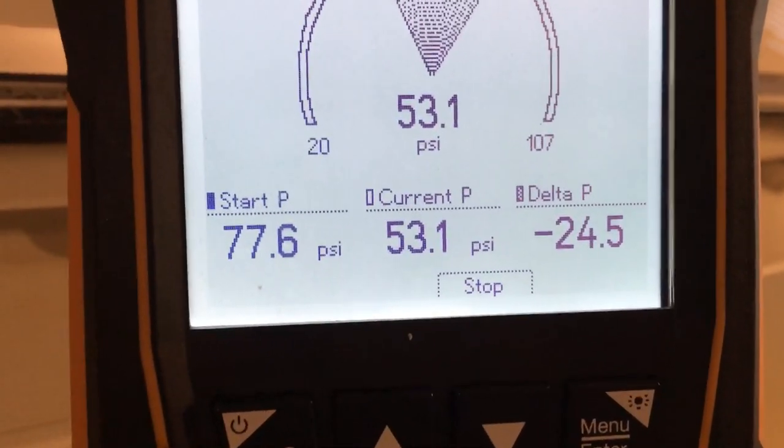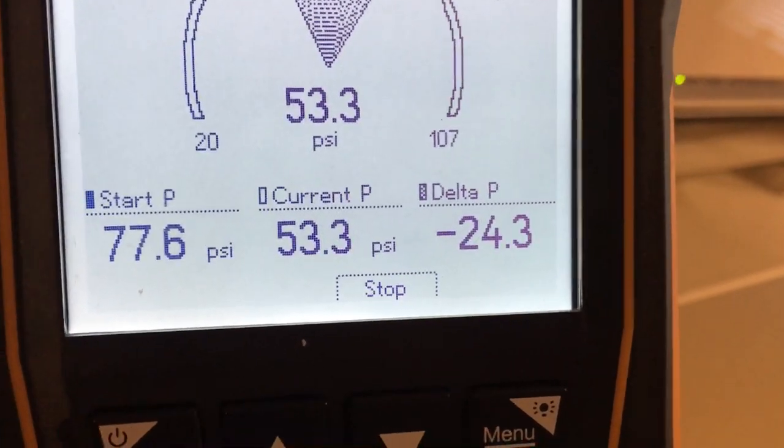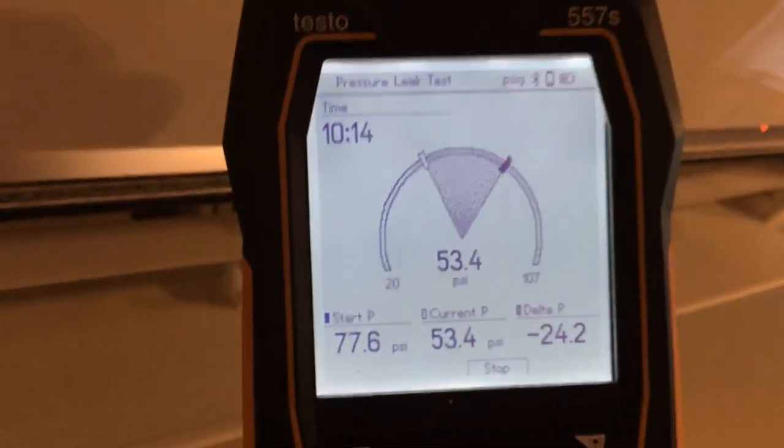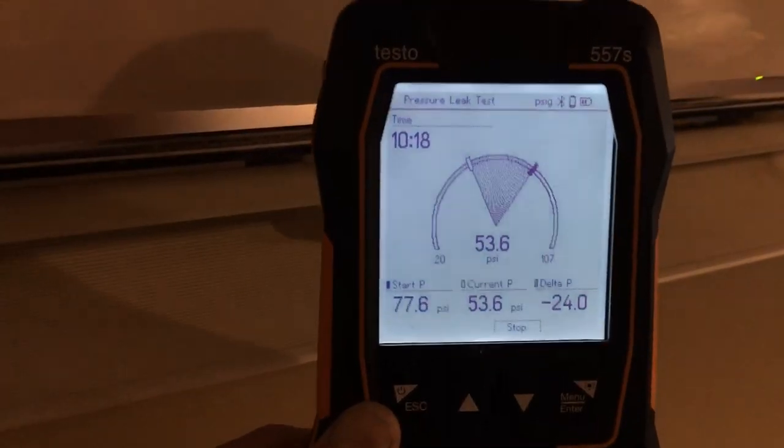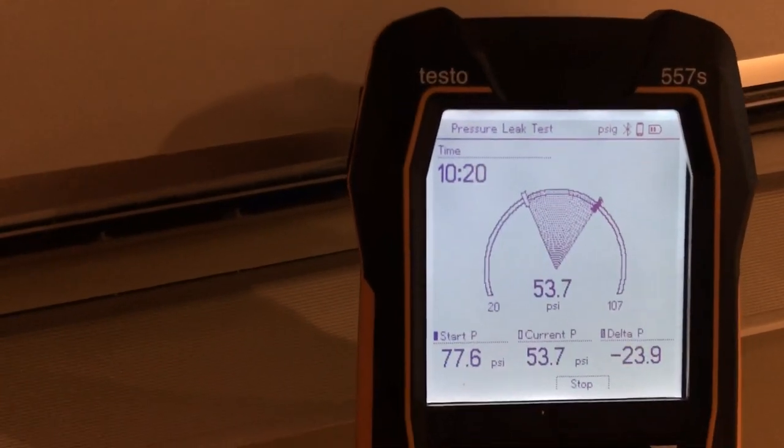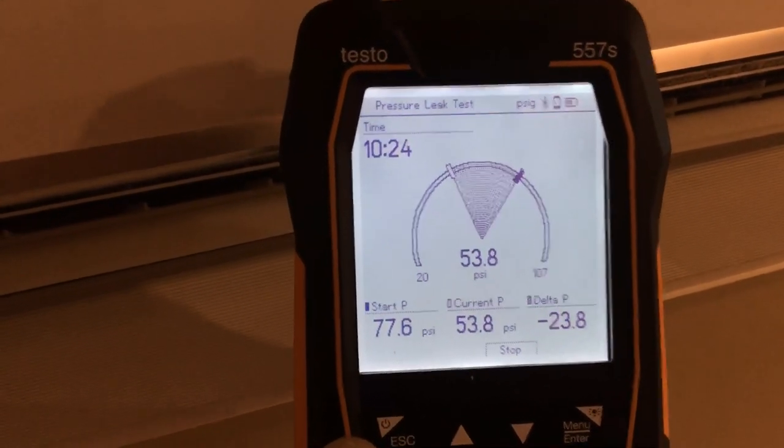I'm currently at 53. So it has dropped 24 PSI right now. So if you were performing a pressure test with refrigerant inside your gauges and the temperature went down, you would think there's a leak, but there's no leak.